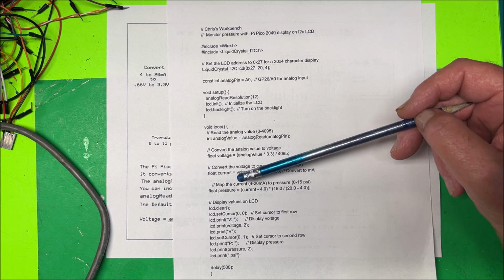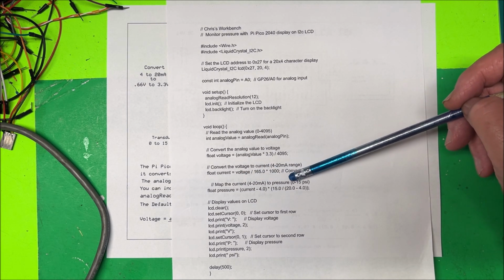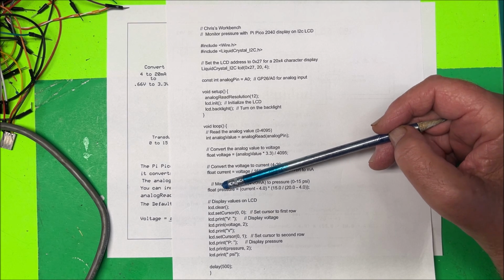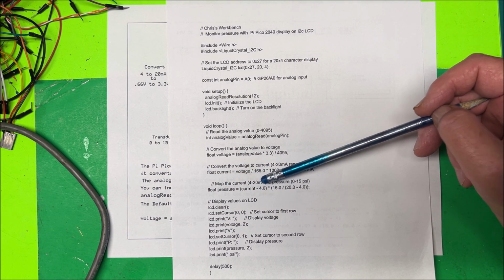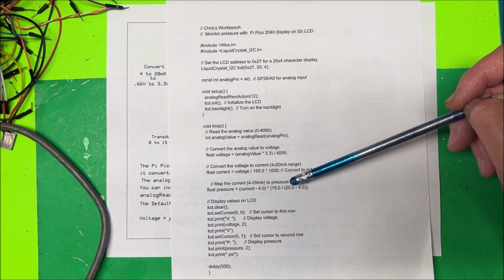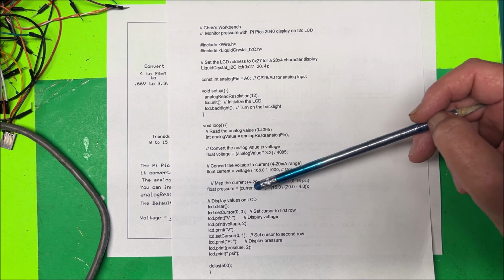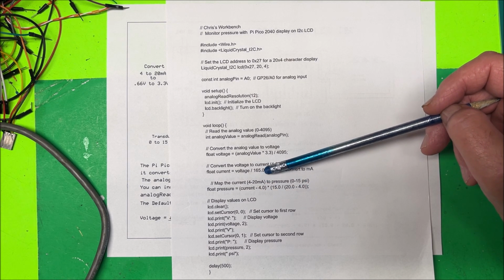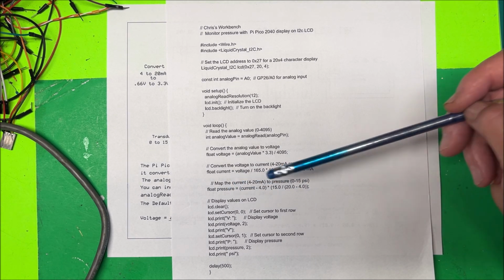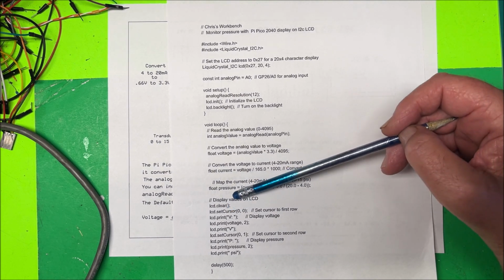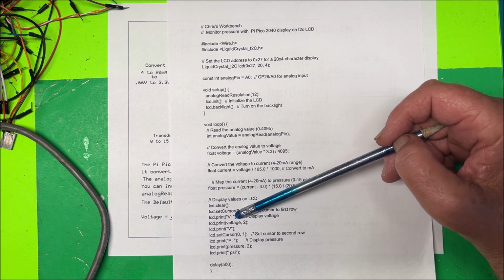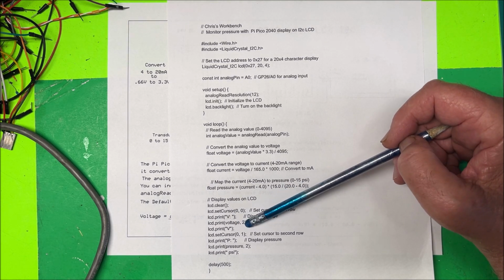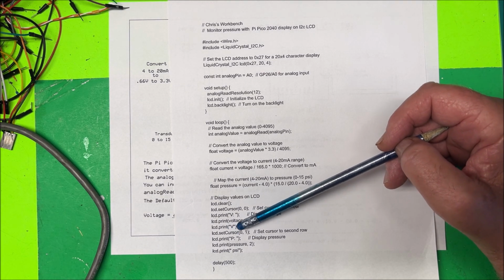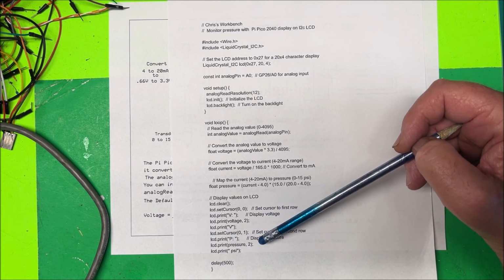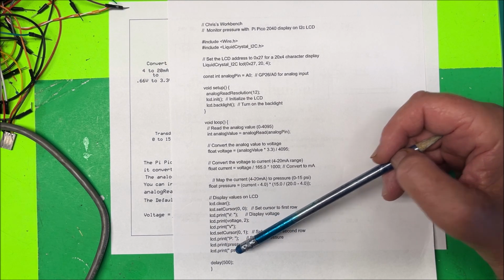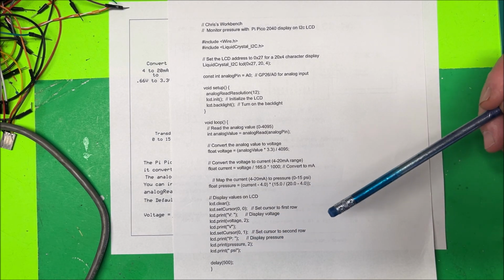And then what we're going to do is we're going to map the current, the 4 to 20 milliamps, to 0 to 15 psi. So float pressure is going to be equal to current minus 4, times 15, divided by 20 minus 4. That's going to convert the current to pressure. And then here we're going to write it to the LCD: clear, set the cursor, print a V, print our voltage with 2 decimal places, then put another V after that. And then we set the cursor again and print a P, and then our pressure with 2 decimal places, and then PSI after that. And then we're going to delay for half a second here.